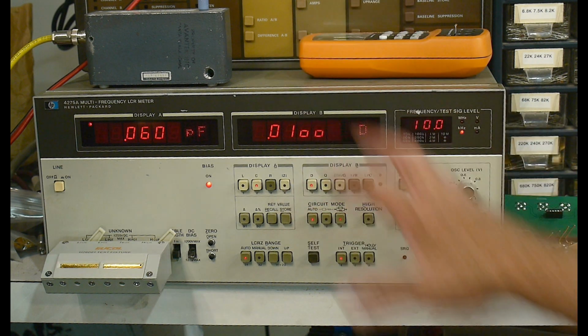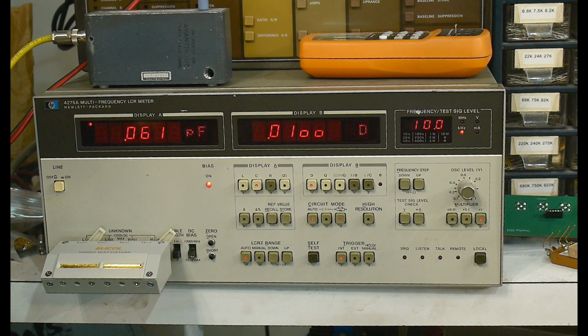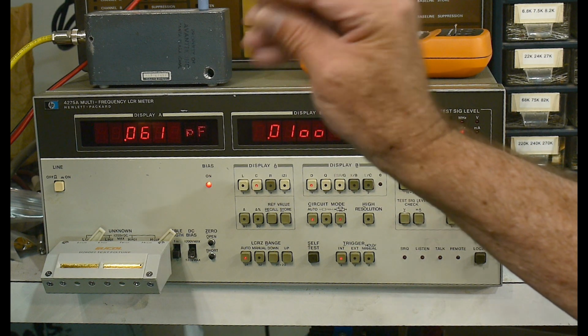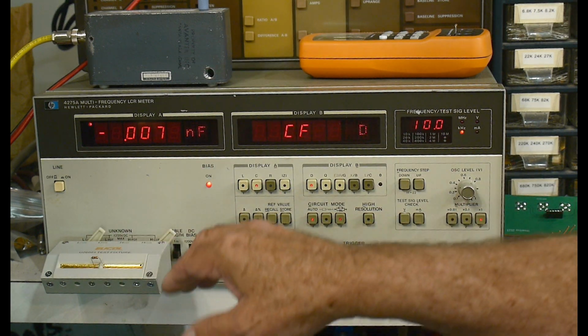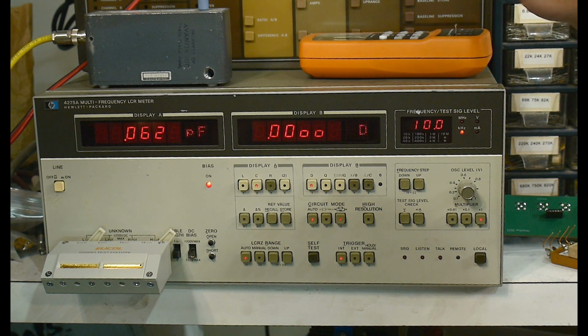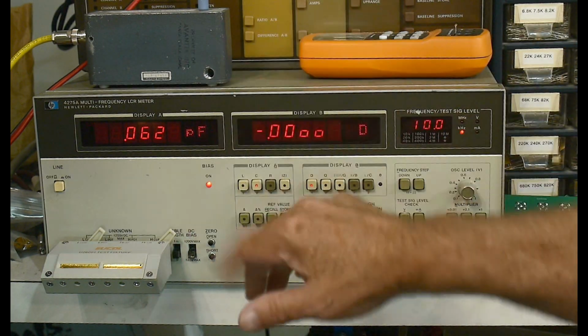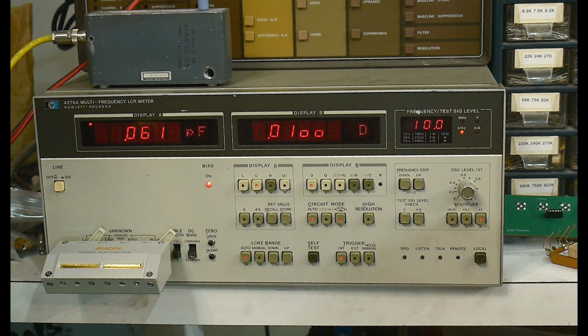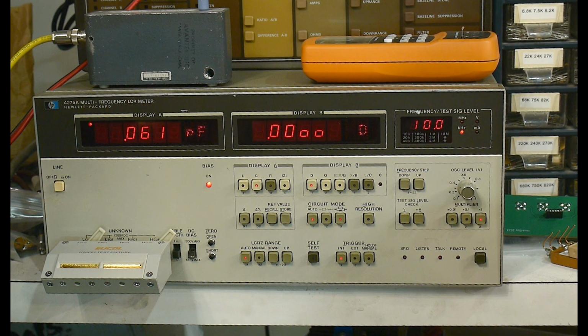So one of the places you reach is you need 4 resistance standards. And it says, please use a specific Hewlett-Packard part number. Well, you don't really need to do that. You just have secondary standards. So, like, I could use this resistor I just used here as a secondary standard, right? I could put it in this machine and measure it, and then put it in this machine and measure it, and then adjust the knobs so the two agree. So that's called a secondary standard. You're using the accuracy of this one. Now, your accuracies are going to stack up. So it's not as good as an absolute standard, but it is a secondary standard.